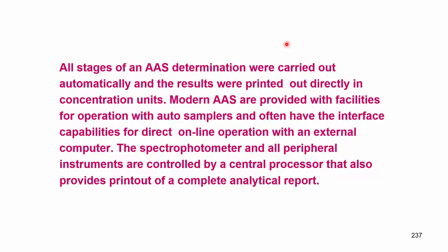Earlier, they used to put the microchips inside the AAS, and if the chip goes, you just have to import. Nowadays, an external computer can access the software and then control the operations. That helps. So, the spectrophotometer and all peripheral instruments can be controlled by a central processor that also provides printout, etc., of a complete analytical report.